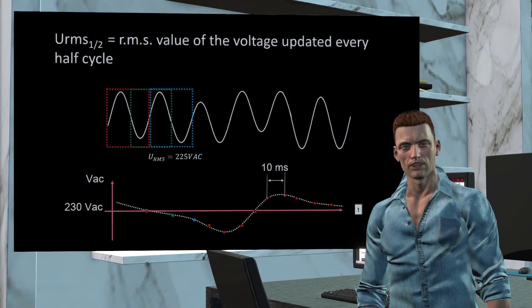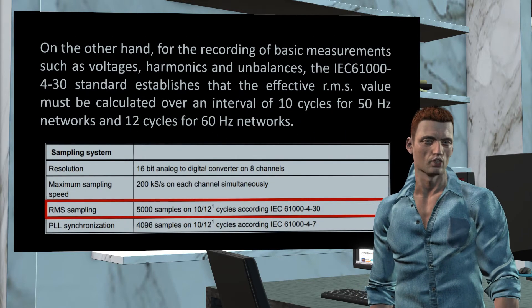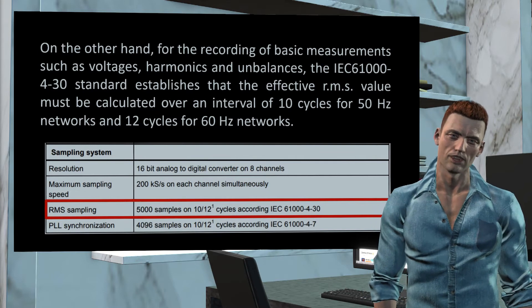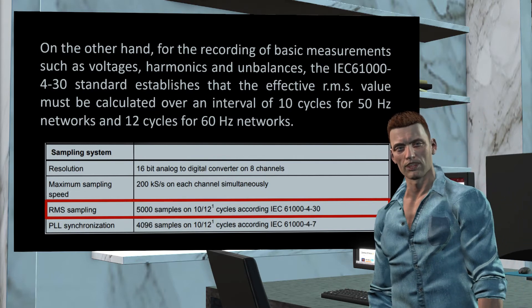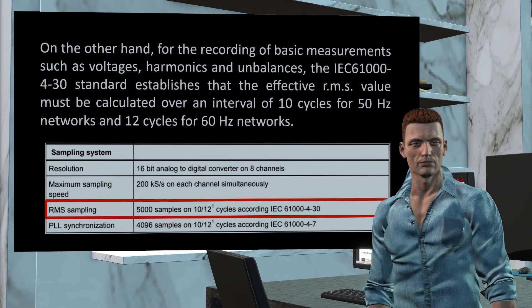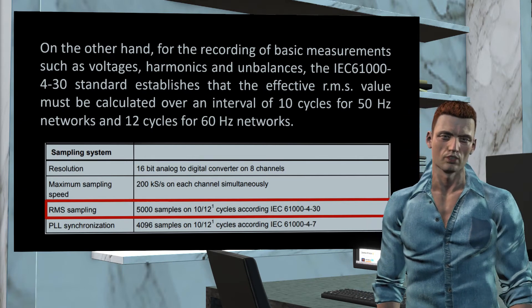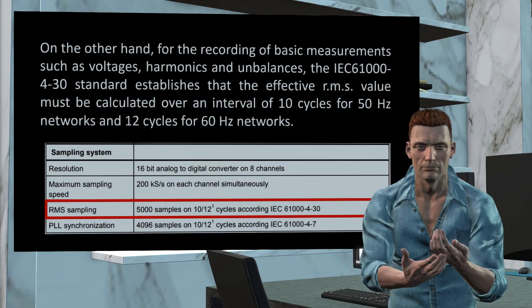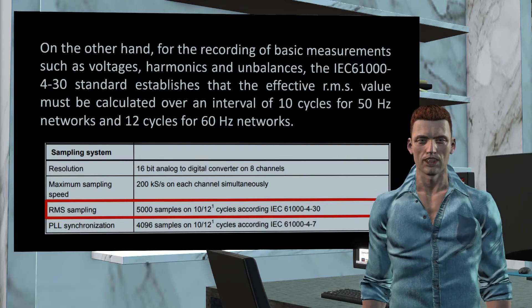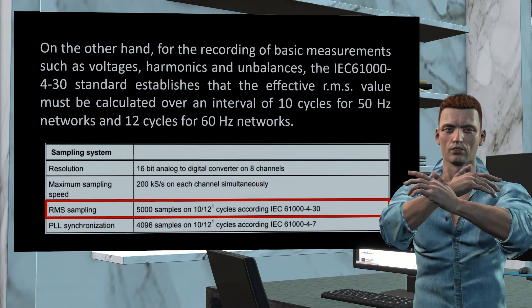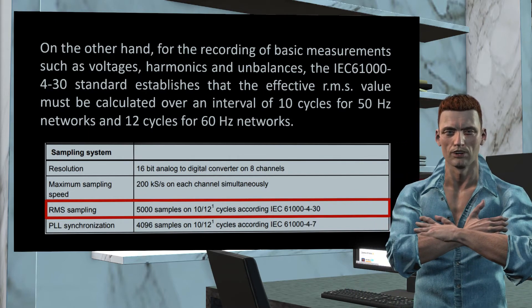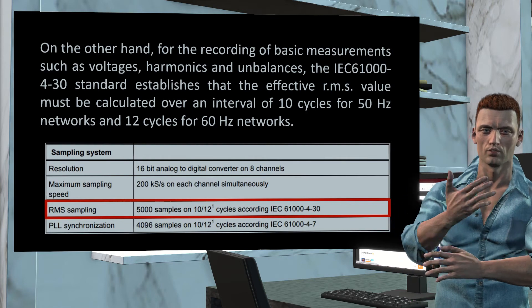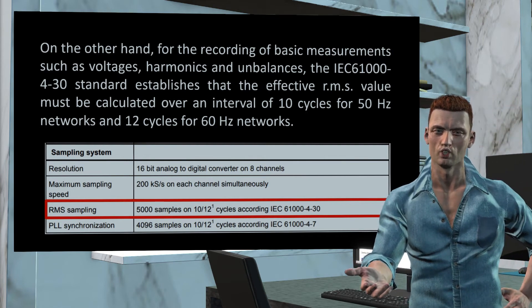On the other hand, the standard IEC 61000-4-30, for Class A analyzers, states that for recording basic measurements like voltages, harmonics and unbalances, it should be used an interval of 10 cycles for networks of 50 Hz, and 12 cycles for networks of 60 Hz. In the case of the Fluke 430 Series 2 analyzers, to obtain the effective values over 10 or 12 cycles, 5,000 samples are taken, that is, 25,000 samples per second.